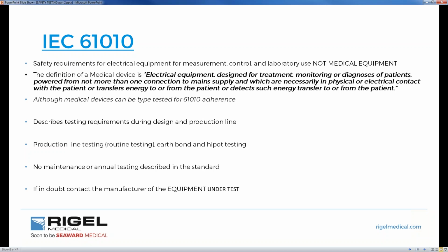Lab equipment, as far as 61010 is concerned, is not a medical device. Although medical devices can still be type tested to 61010 adherence, that is important. So it can be part of the process of a medical device. Let's not ignore that. The standard itself describes testing requirements during the design and production phase of a medical device or any electrical device. Production line testing, not so much routine testing, where you would use high pot testing, which is high potential, and earth bond. No maintenance or annual testing is described in the standard.